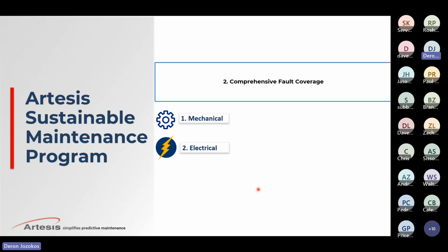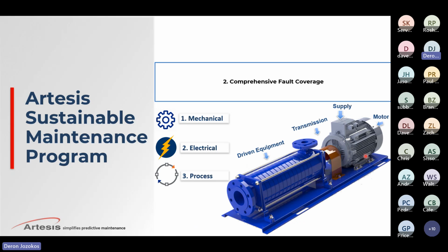We're also able to identify all the electrical faults, upstream, downstream. So, incoming power supply issues, voltage fluctuations, motor health. So the whole condition of the rotor, stator, the windings, we're able to see all of that, even corrosion at some terminal blocks at a local disconnect, those types of things. Also process-related faults. So it takes it even further and is able to identify process-related faults, such as a leaking valve downstream, and the motor's working harder to keep up a certain pressure or something like that. Cavitation on a pump. But also you wouldn't see the cavitation in a fan system, in the plenum. You would see different types of faults. So it learns what is the normal process and is able to identify process-related faults.